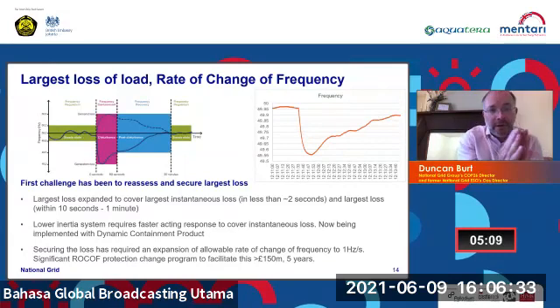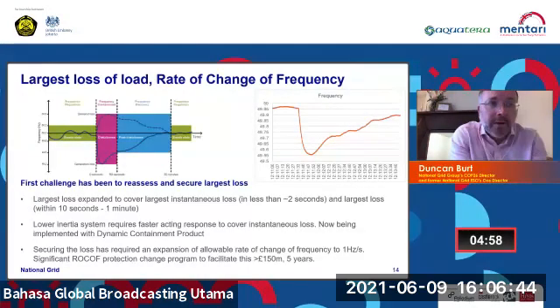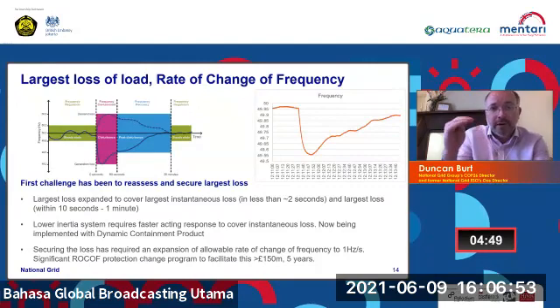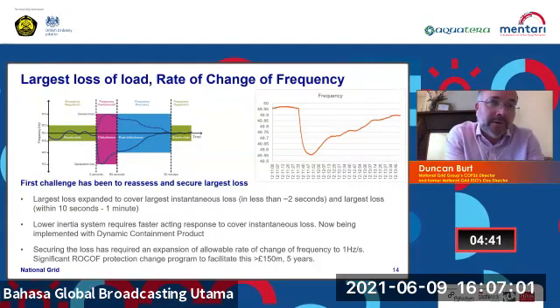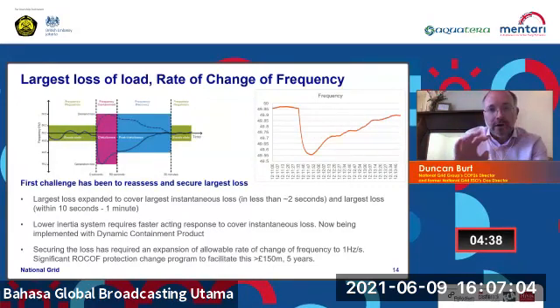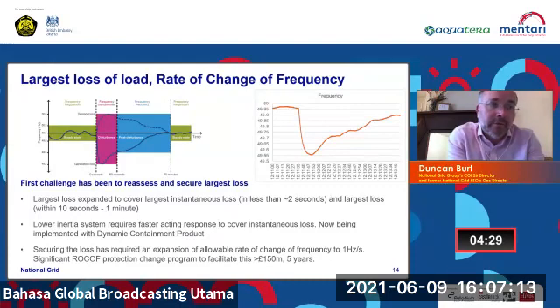In fact, we've split the largest loss limit into both an instantaneous loss, which is the complete loss of power infeed in less than 2 seconds, and a residual largest loss, which would typically occur over 10 seconds to a minute. For example, our largest nuclear power stations tend to fall off quite slowly. You'll lose the reactor, the turbine will slow down gradually, the boiler temperature will drop, and then it will safely shut down. That's a very different, gradual loss, as opposed to the instantaneous opening of a breaker and the instantaneous removal of that power infeed from the system.